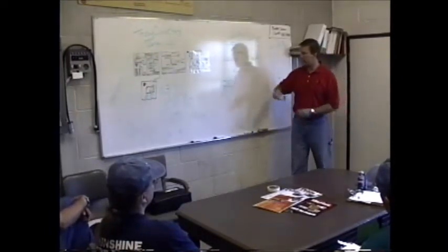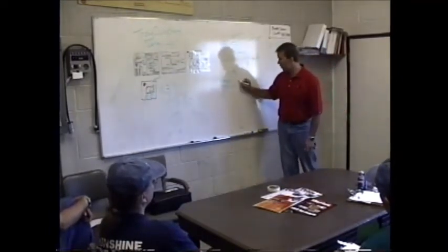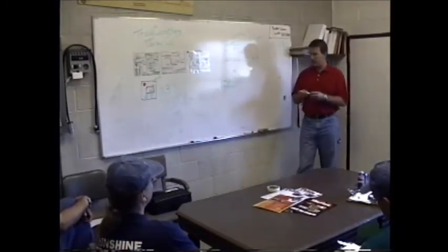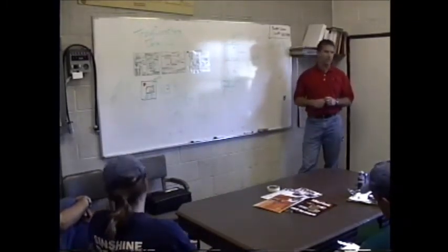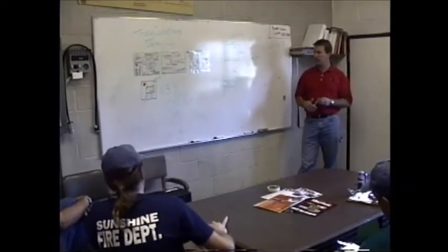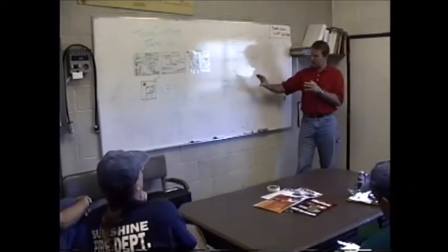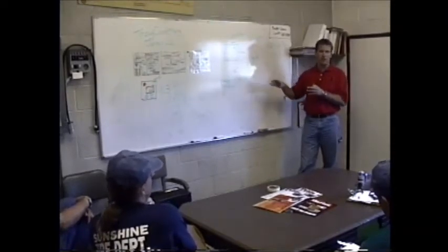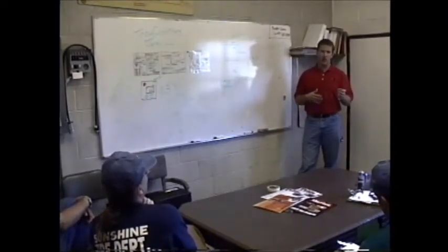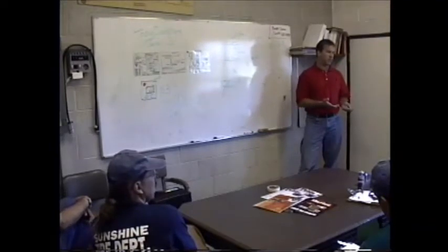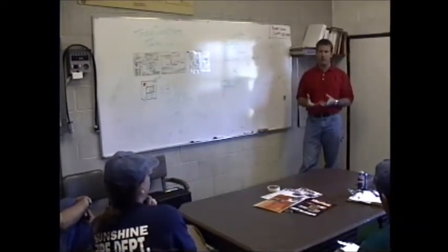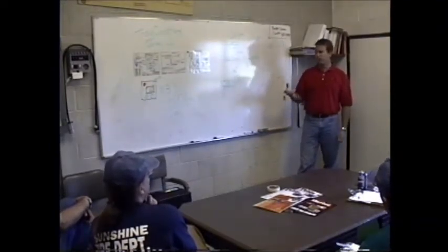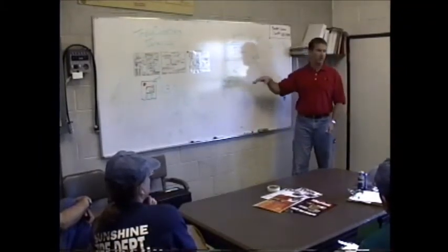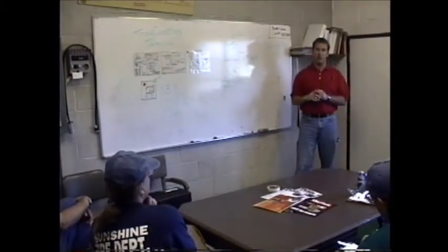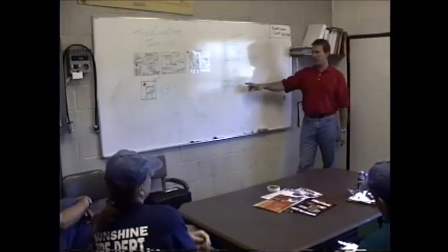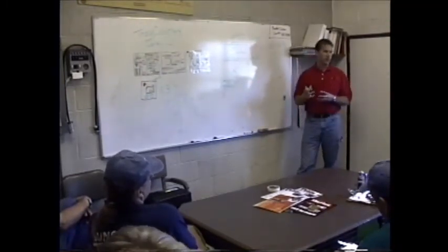But most of the tips we go down to maybe 1 1/4 or 1 1/8. Some people even go down smaller than that with CAFS. The smaller you go down, the more it's going to squeeze those bubbles as they're traveling through that nozzle and pop some of those bubbles as they travel out onto the fire, which is going to be fine for firefighting. But if you're really trying to make the fluffiest foam possible, you want to almost screw all these tips off and just let that foam come right out of the end of the open butt of that nozzle, so that you don't put any added restriction on the end of that stream that's coming through.